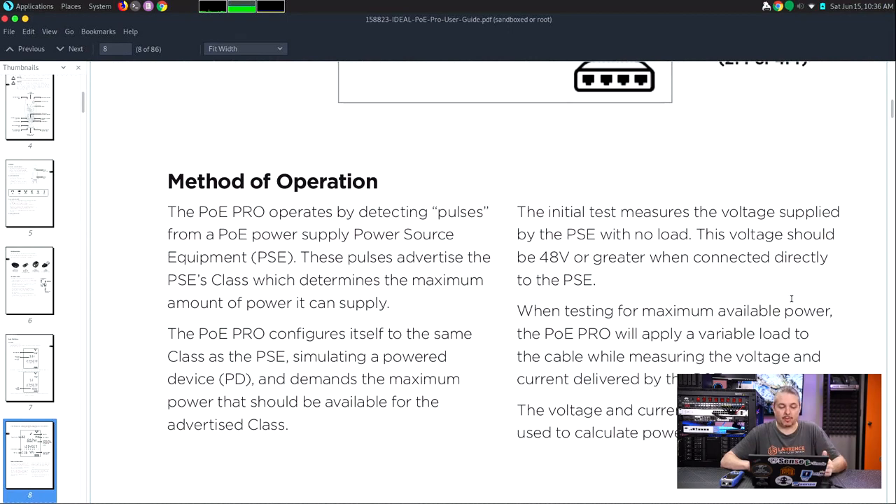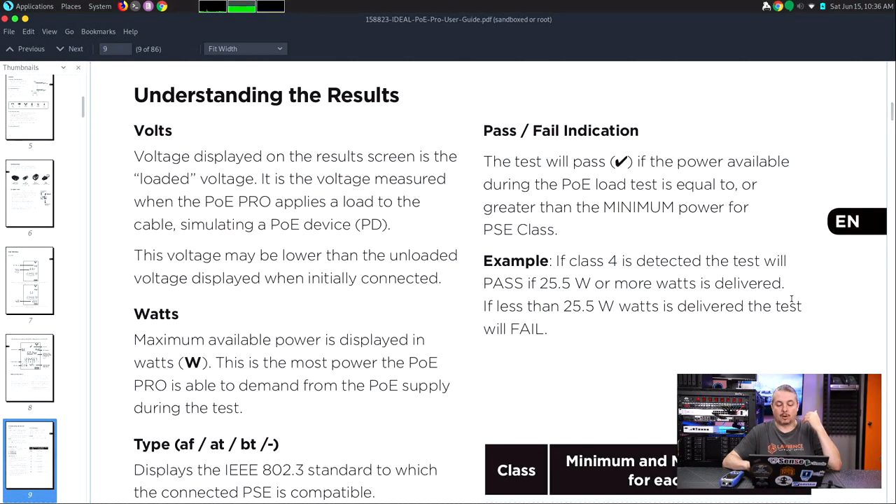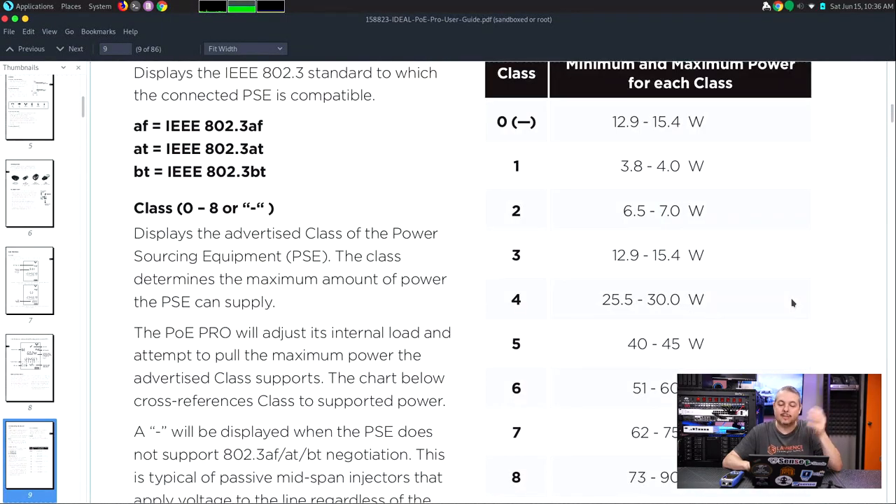The PoE Pro operates by detecting pulses from PoE power source equipment. These pulses advertise the PSE's Class, which determines the amount of maximum power it can supply. If you're not familiar with active PoE or how a system works — like the unified PoE switch we're going to be showing — it allows different classes to be identified. There are several different types and classes of PoE determining voltage. When it does the PoE testing, it's not just testing whether wattage comes out — it identifies the class and passes or fails whether it provides voltage as the class it identified.